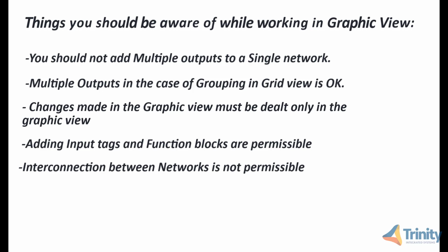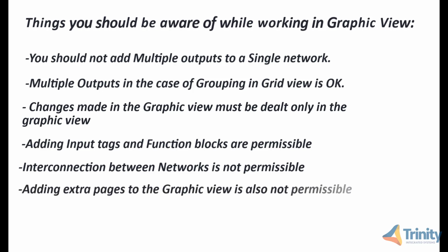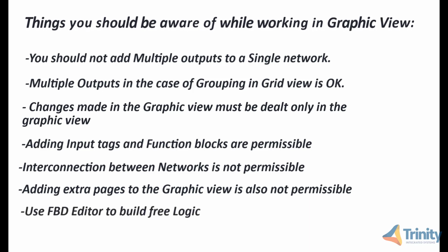Interconnection between networks is not permissible. Adding extra pages to the graphic view is also not permissible. If you want to build free logic in iDefine, you can use FBD editors instead of cause and effects.